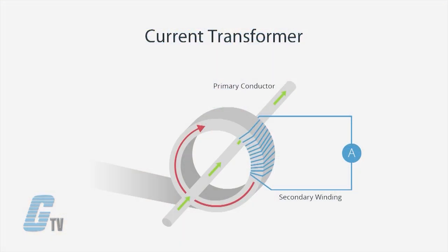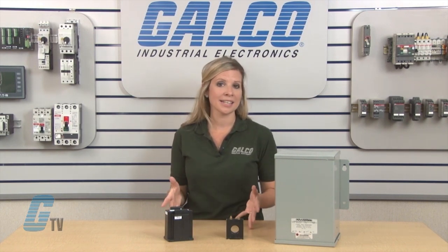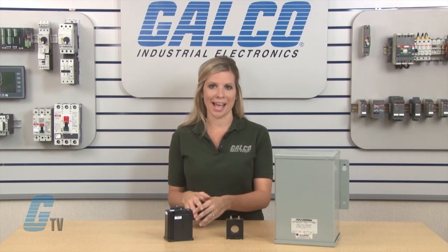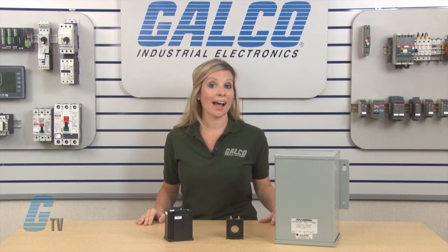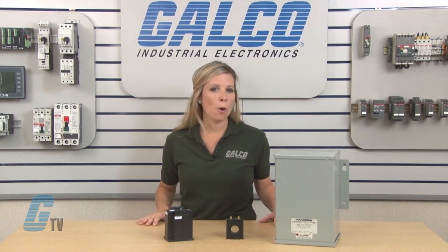A current transformer has a primary coil of one or more turns of heavy wire. It is always connected in series in the circuit in which current is to be measured. The secondary coil is made up of many turns of fine wire, which must always be connected across the ammeter terminals. There is a wide range of possible primary voltages because the device can be connected to many types of conductors. The secondary must always be available to react with the primary to prevent the core from becoming completely magnetized.